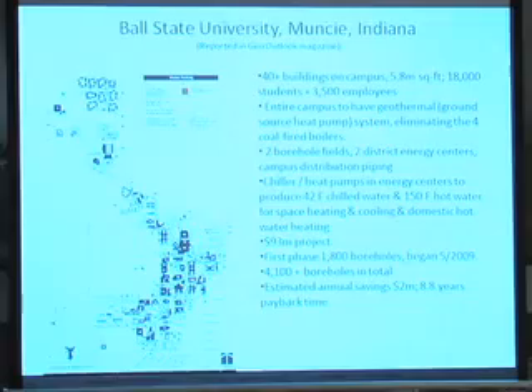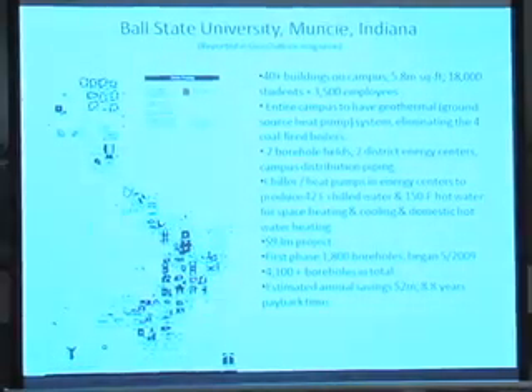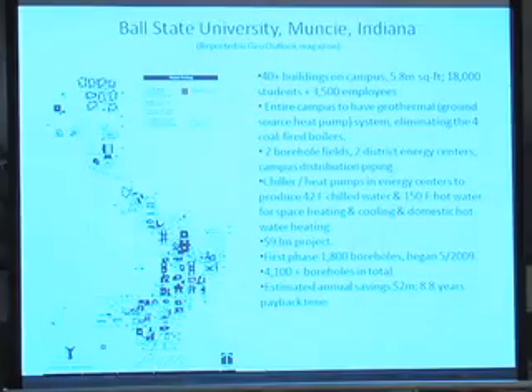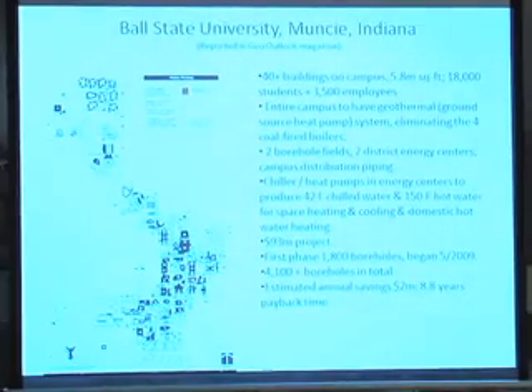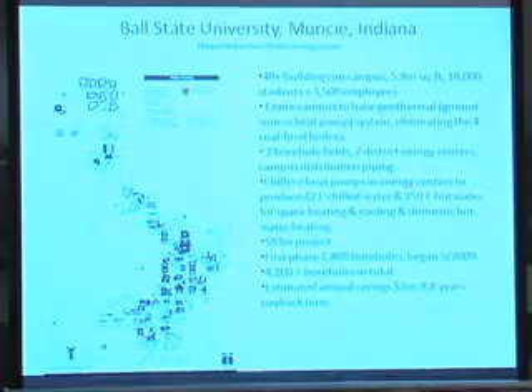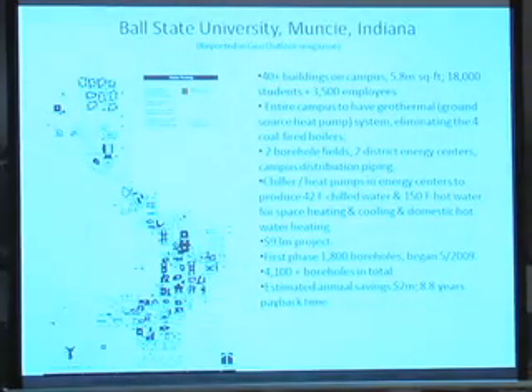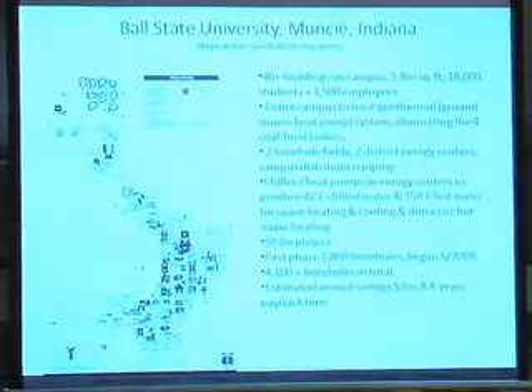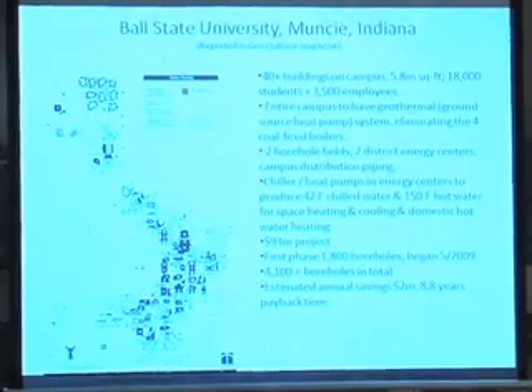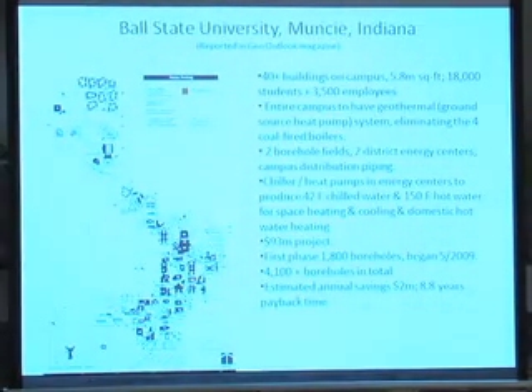They used to have 4 coal-fired boilers. You can imagine the big, dirty chimneys out of that. The chillers and heat pumps in the energy centers produce chilled water at 42 degrees and 150 degree hot water for space heating and cooling, and also domestic hot water. $93 million project. First phase, they drilled 1,800 boreholes. Project began in May 2009. They're going to have a total of 4,100 boreholes once the project is finished. Estimated annual savings $2 million, less than 9 years of payback time.